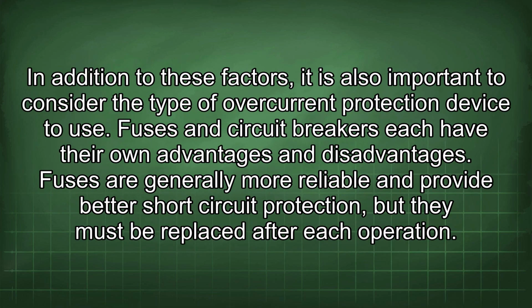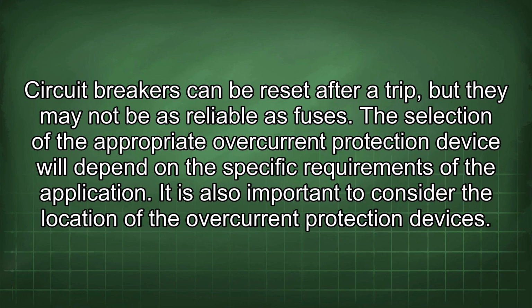In addition to these factors, it is also important to consider the type of overcurrent protection device to use. Fuses and circuit breakers each have their own advantages and disadvantages. Fuses are generally more reliable and provide better short-circuit protection, but they must be replaced after each operation. Circuit breakers can be reset after a trip, but they may not be as reliable as fuses. The selection of the appropriate overcurrent protection device will depend on the specific requirements of the application.